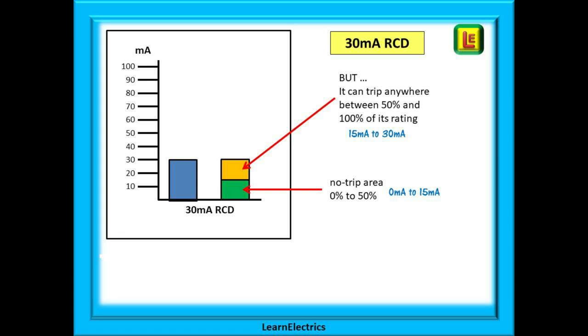In practice it will often be around 25 milliamps. A residual current between 0 and 50 percent should not cause the RCD to operate which is why we do a times half RCD test when verifying circuits.